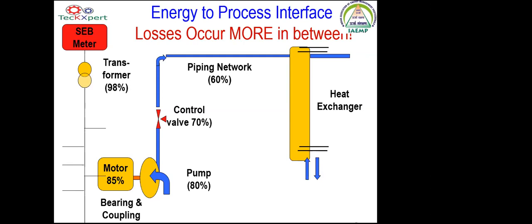So much loss is happening on the pumping side and the controlling side, especially the piping network side. These are the areas where the material of construction of the piping has to be checked during the audit, to know where the MOC can be improved, especially on the aluminum type of piping in the compressed air header. This MS or GI type of piping is going out and getting obsolete in industry, especially in compressed air. With rigid PVC pipes for water, the friction loss can be reduced, and straight away around 15 to 20% energy saving is possible by going for rigid PVC piping, especially on water circulation. All these aspects we will discuss during the study at the time of audit, but these are the inputs we need from the industry.